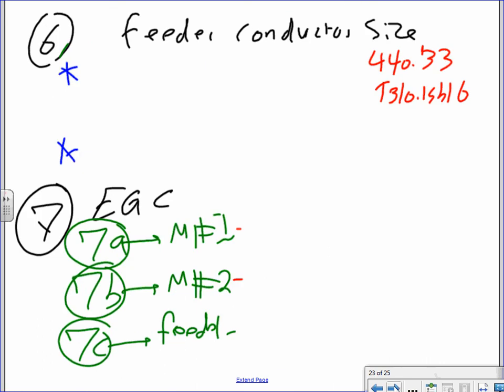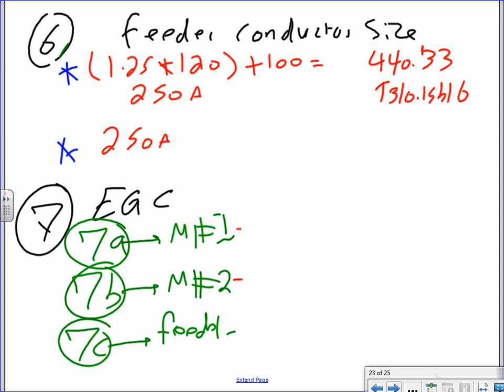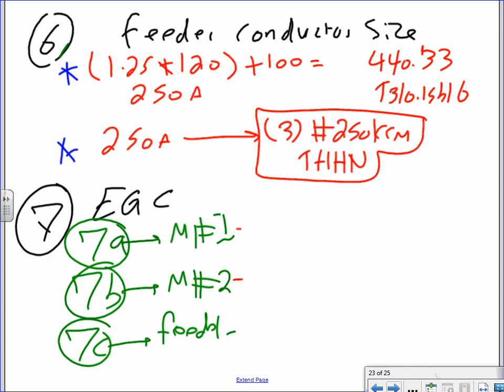Feeder conductor: 1.25 × 120 (largest) + 100 = 250 amps → Table 310.15B16 → three conductors, 250 kcmil THHN. If in a wet location, use THHW or THW.